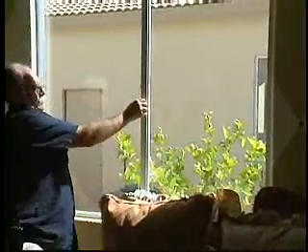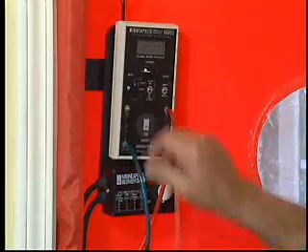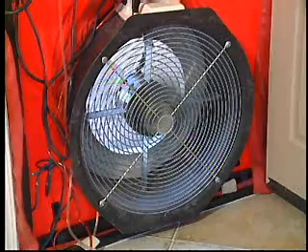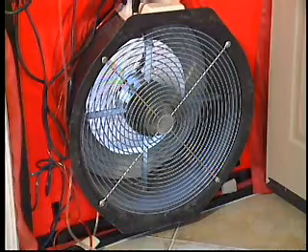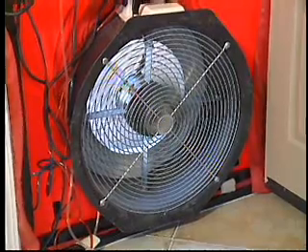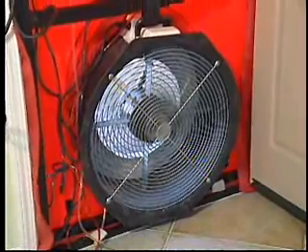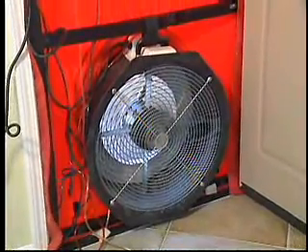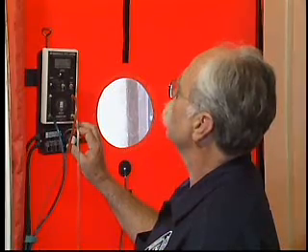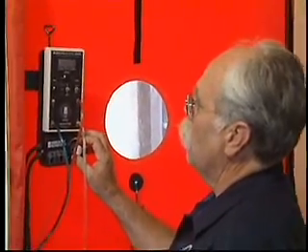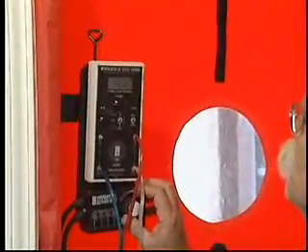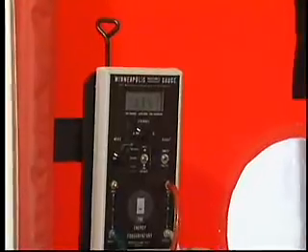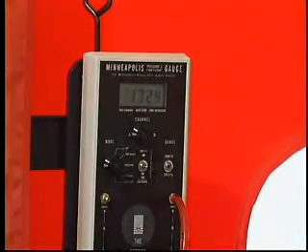Okay, so then you turn on the fan, and I guess you could pressurize or depressurize. You like to pressurize homes? I like to pressurize homes, but depressurizing just depends on what's going on with the house, Steve. Yeah, so this basically forces air through the house. The manometer helps you quantify that. Yes, sir. And what are the typical ranges in leakage that you find on California homes? Oh, I've got them as low as 400 and up to 9,000 cubic feet per minute, Steve. Really? Well, that's a wide range. Now, what's typical for a 2,000 square foot house? Oh, around 1,500 to 2,500 cubic feet per minute.